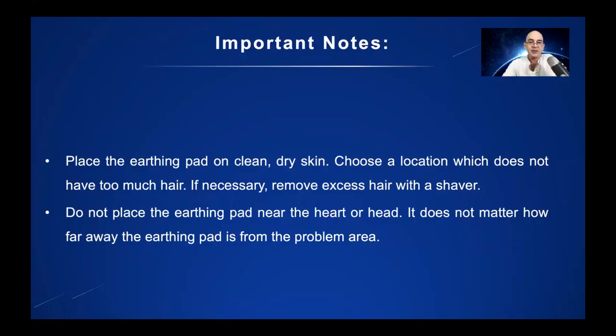Okay, so this just goes through other information. You place the earthing pad on clean, dry skin because the electrical contact has to be good. You choose a location which does not have too much hair, and if necessary, remove the excess hair with a shaver. That's why I didn't do that in the video. You do not place the earthing pad near the head or the heart. It does not matter how far away the earthing pad is from the problem area.